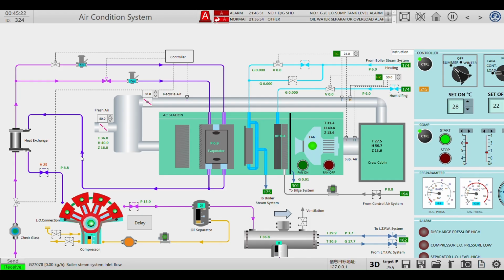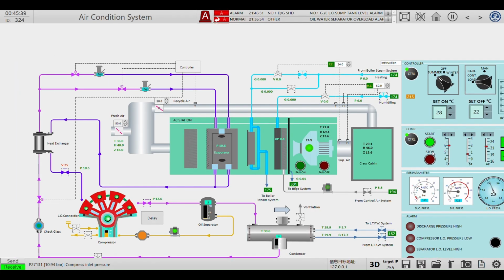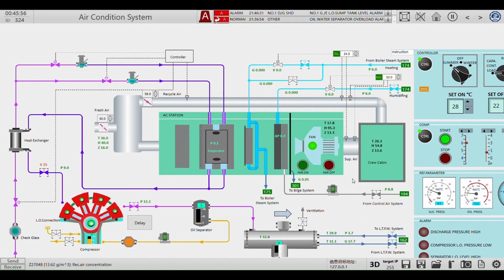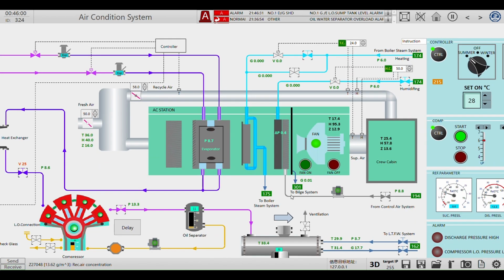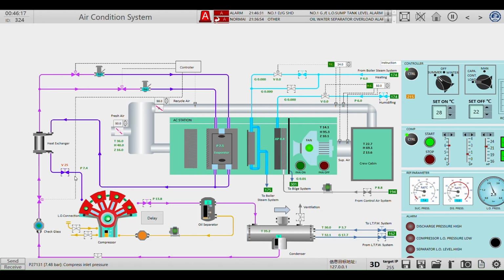You can see the main difference between the refrigeration system and the AC system. You will find that you maintain a higher suction pressure because we are not maintaining a low temperature here. You cannot actually maintain below 20 degrees Celsius. Whatever comes, we have to maintain the suction pressure such that the saturation temperature is always above 0 degrees Celsius, because on AC systems you don't have a defrost system. So we make sure that whatever the pressure is here, the corresponding boiling point of the refrigerant we use does not fall below 0 degrees Celsius.